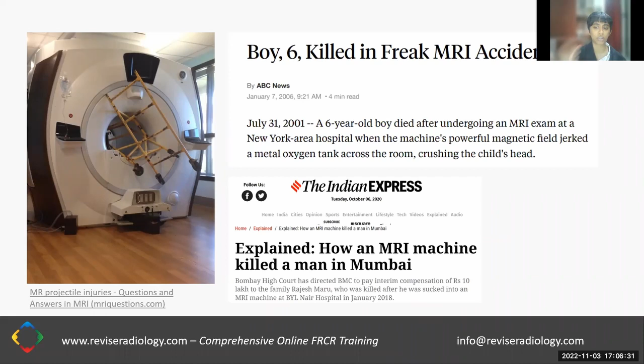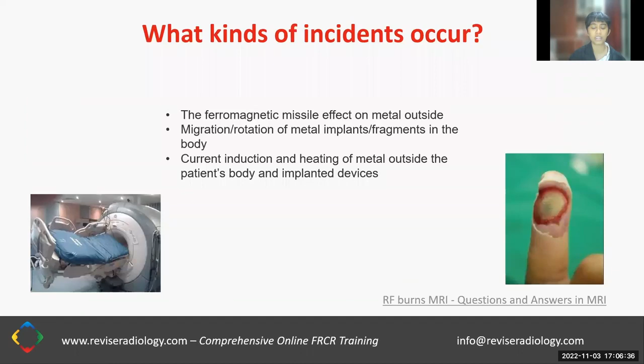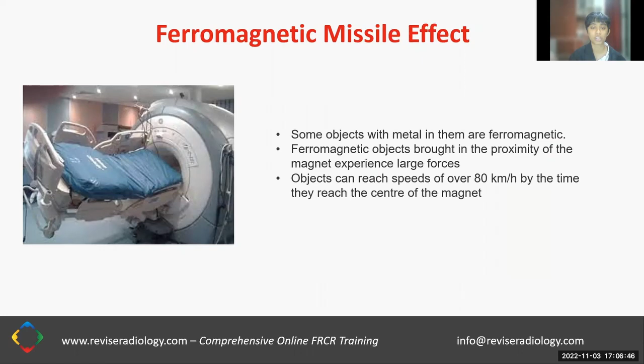So how do we prevent this ferromagnetic missile effect from happening? In the incident that we saw earlier, where a 6-year-old boy died, the machine's magnetic field had hurled a metal oxygen tank across the room, crushing the child's head. So metal oxygen tanks are strictly not allowed in the MRI controlled area. If oxygen tanks are required, they provide oxygen through tubes which are suitable for use in the MRI controlled area.